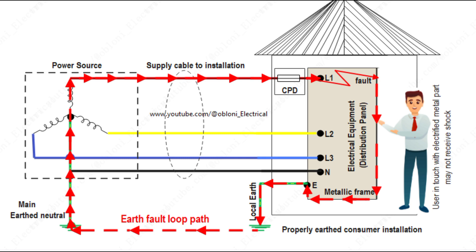For protective devices such as RCDs to operate effectively during an earth fault, this path must allow a substantial amount of the fault current to flow back to the supply source. If this path is not able to complete, then whatever protective devices you have in your circuit will not operate, including RCDs. So we have to make sure that the resistance of this path is as low as possible to allow a substantial fault current to flow back. This is why it is very important to do your earthing effectively.